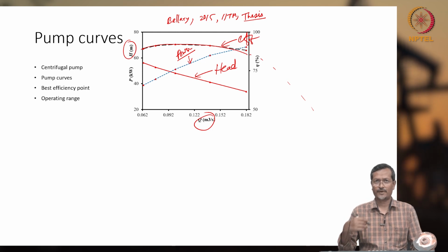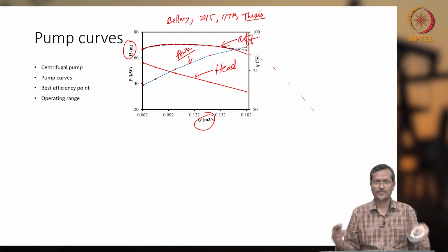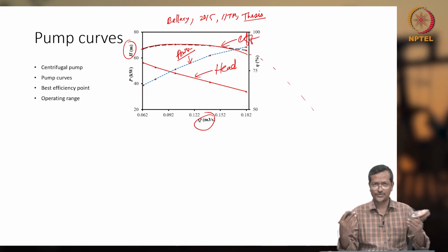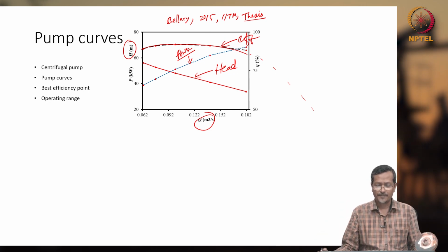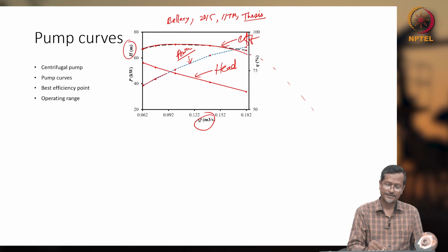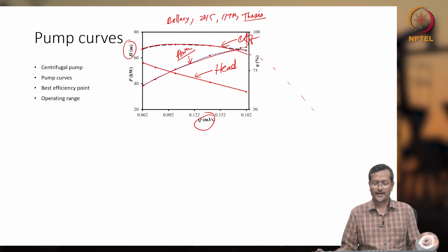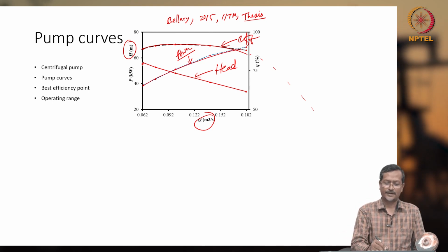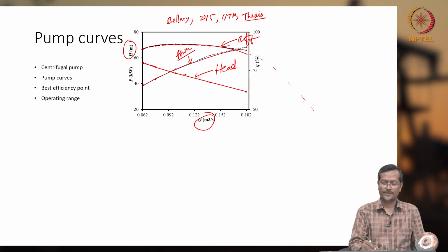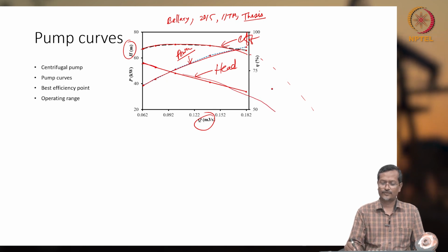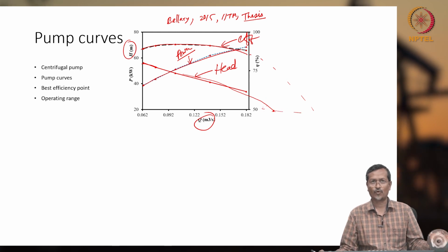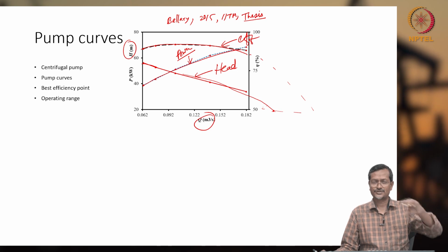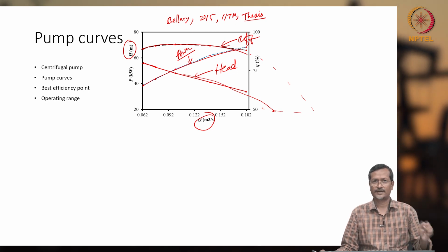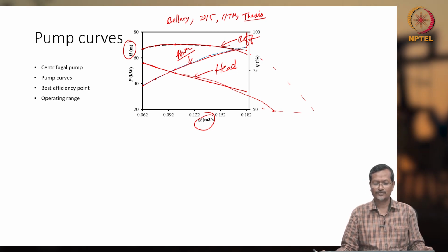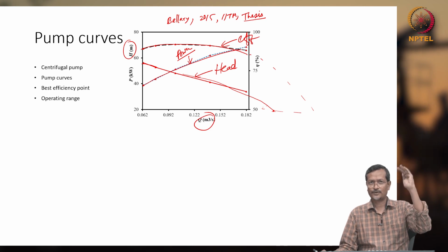System curve means how much power it is taking, how much friction it is crossing, so how much total energy is being consumed by the pump; that is what this line is showing. Okay, and head, I said, will go like this and it will be 0 somewhere, so H should be 0 somewhere. Okay, that will be absolutely open flow, when there is no restriction in the exit valve, so you are getting maximum flow rate. So at that time your pressure on the pressure gauge will be lower.